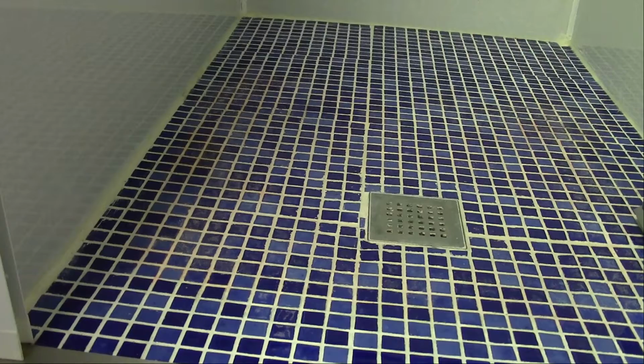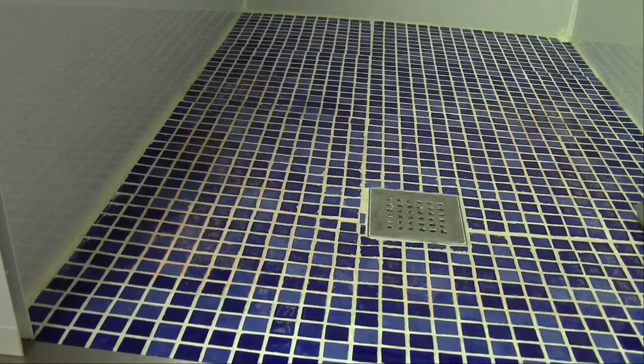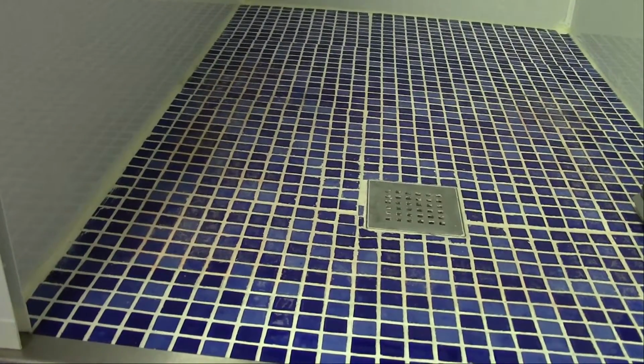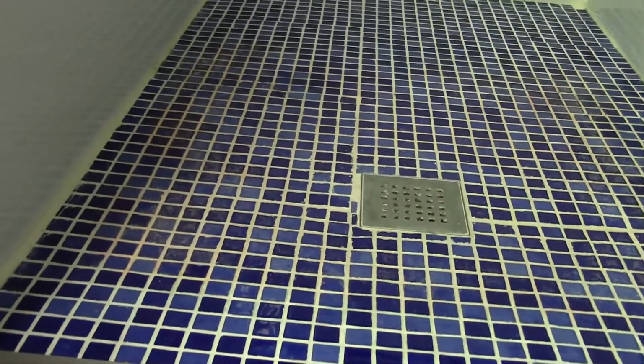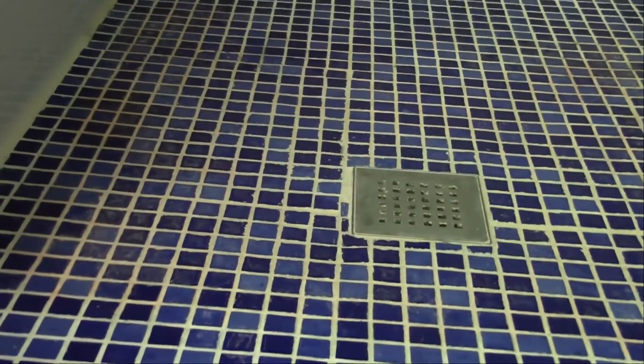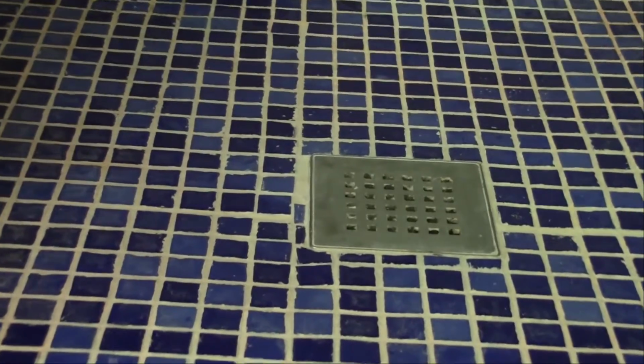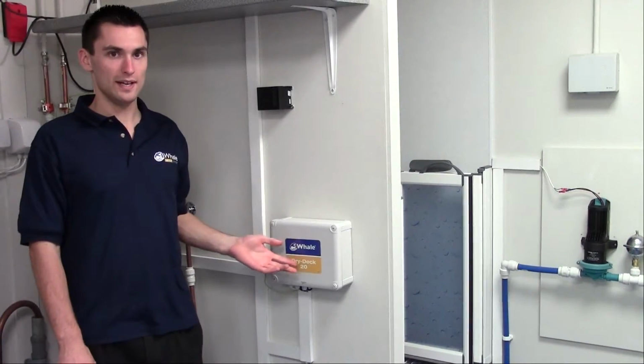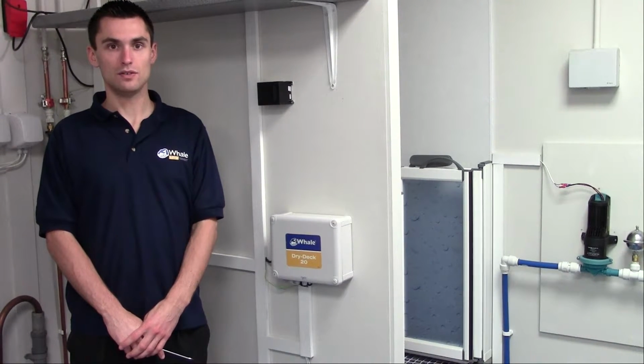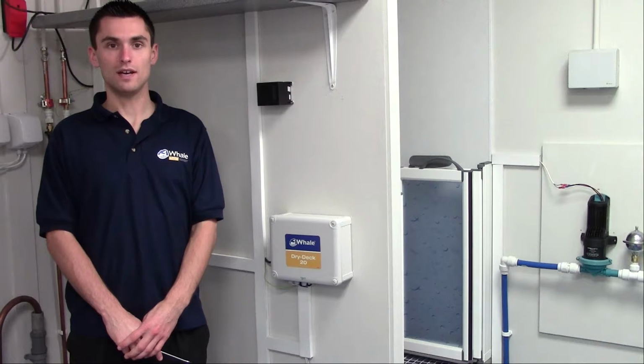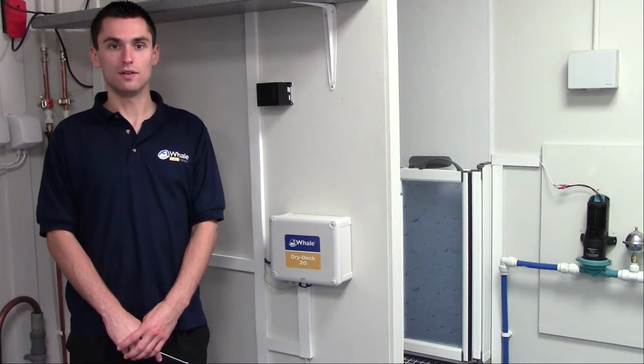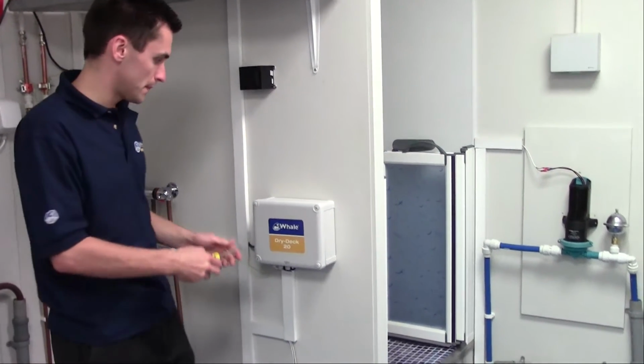To ensure that the system operates as designed, there must be an adequate fall in the tray or wet floor, with a minimum of a 1 in 40 fall to the gully. Here we have the Whale Dry-Deck 20 control box. To access the control panel we need to unscrew the 4 screws with a flathead screwdriver and the front panel lifts off.